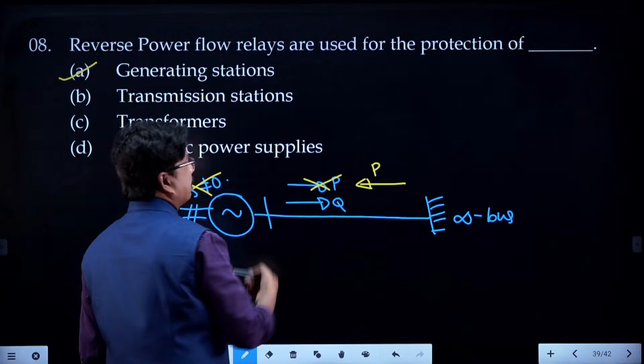So, this reverse power is trying to rotate the turbine which is coupled to the generator in the reverse direction. Because of that rotation, the turbine blades may be damaged, but actually turbine inertia is very high. How a generator can rotate the turbine is not possible. Suppose if it is doing that, turbine will be damaged, but the machine does not know it cannot rotate the turbine. To do that, it will take huge amount of current from the infinite bus, due to which the transmission system will be damaged, right.